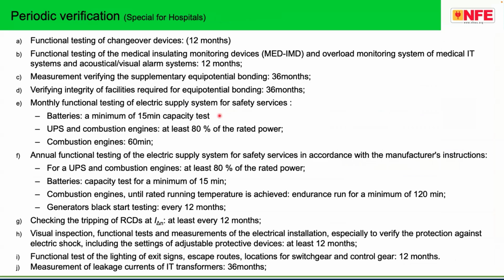Periodic verification is very much necessary in medical locations, especially, with some additional requirements, not in a normal building, in hospitals. Something more is required. Example, functional testing of the changeover device should be made every 12 months, because if this device is not working, you are in deep trouble. Functional testing of the medical IMD, insulation monitoring device, and the overloading and the current of the medical IT transformer has to be measured. Measurement verifying the supplementary equipotential bonding every 36 months. Main equipotential bonding again 36 months.